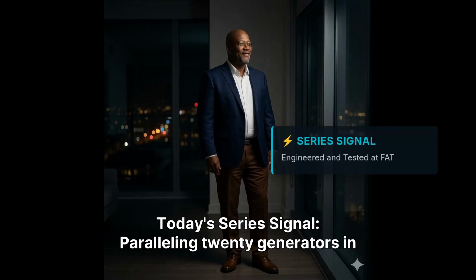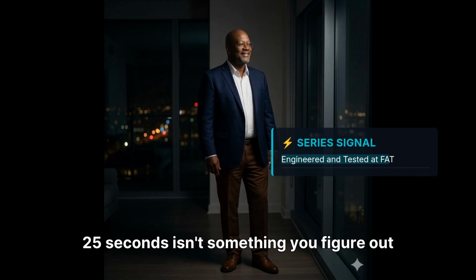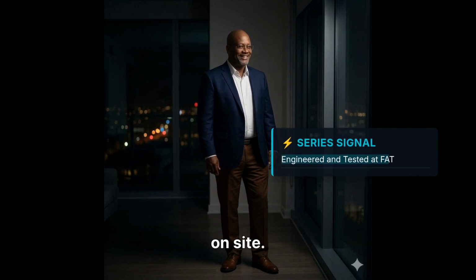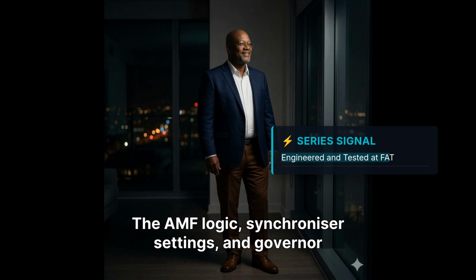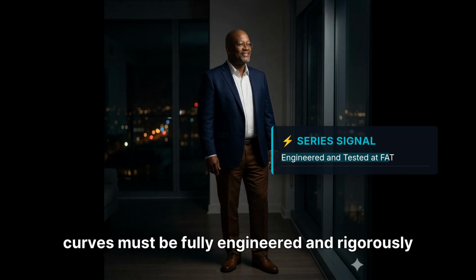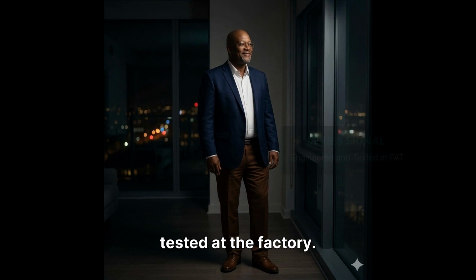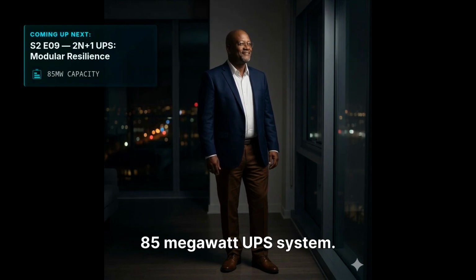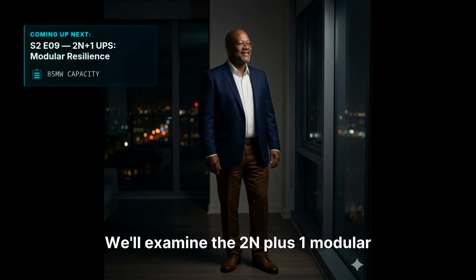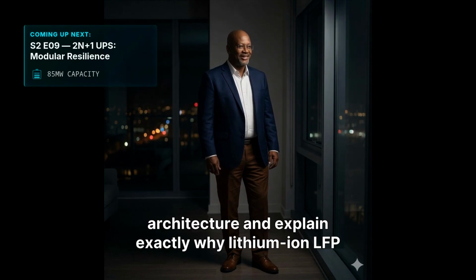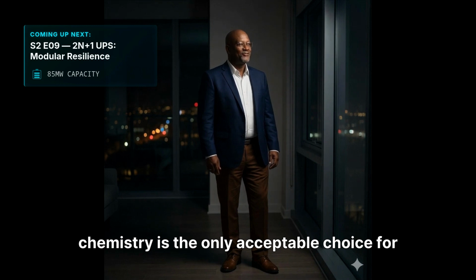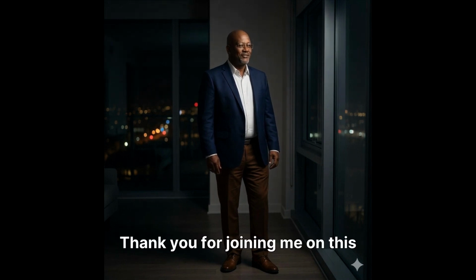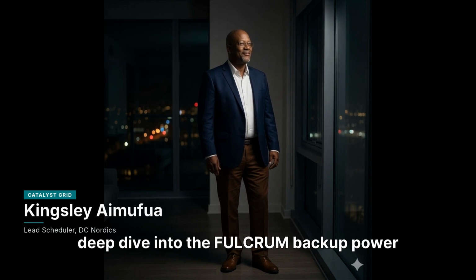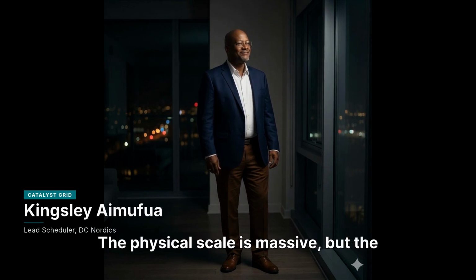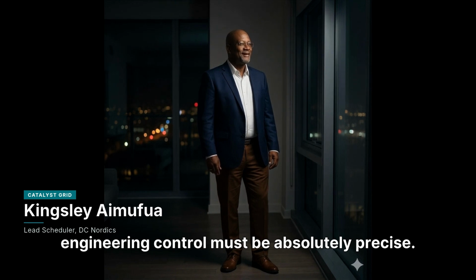Today's series signal, paralleling 20 generators in 25 seconds, isn't something you figure out on site. The AMF logic, synchronizer settings, and governor curves must be fully engineered and rigorously tested at the factory. In episode 9, we move to the 85 megawatt UPS system. We'll examine the 2N+1 modular architecture and explain exactly why lithium-ion LFP chemistry is the only acceptable choice for hyperscale bridging. Thank you for joining me on this deep dive into the FULCRUM backup power system. The physical scale is massive, but the engineering control must be absolutely precise.